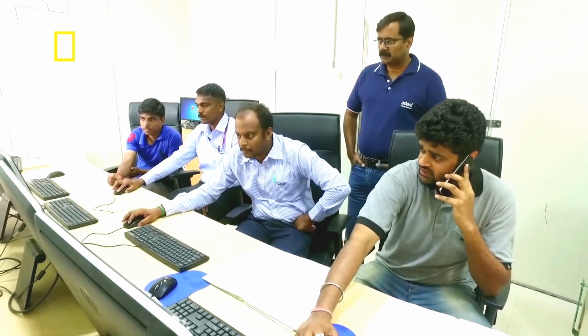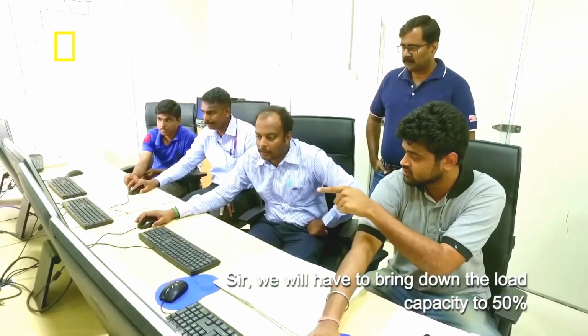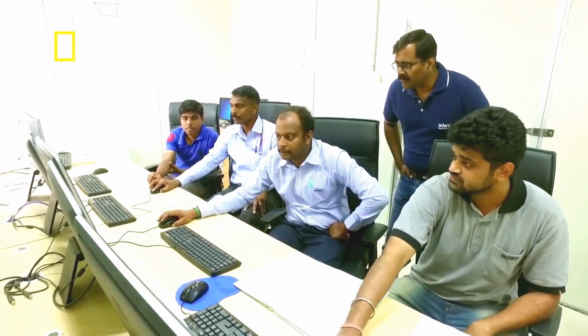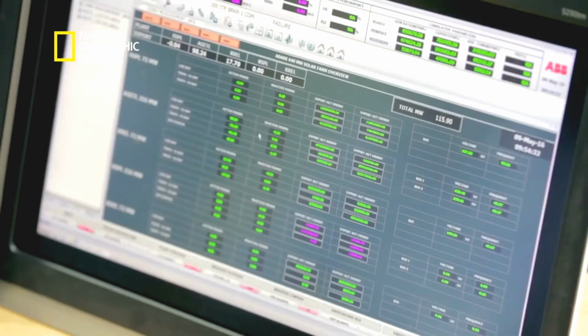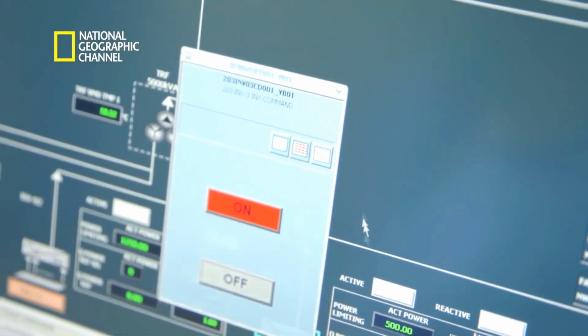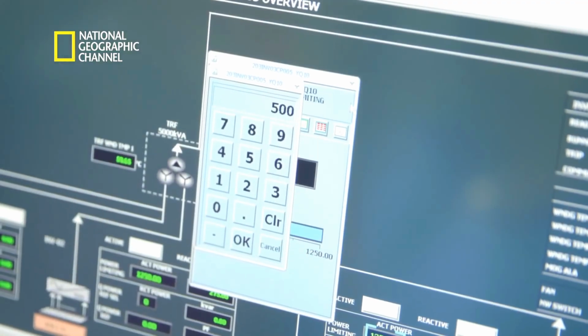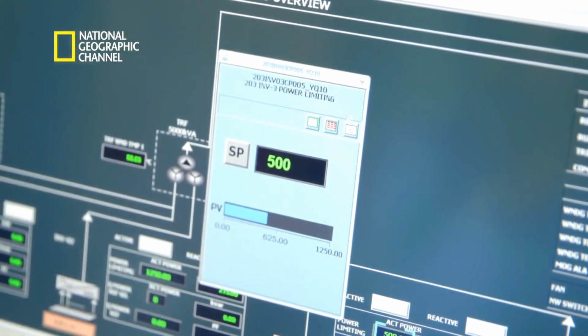Okay sir, we'll reduce it up to 50% of the present load. We are at 50 megawatts now, and we have to make it 25. Let's set the point to 25 megawatts now. Done? It's responding? Perfect. Now, suppose my inverter is generating 1 megawatt at a given point of time, and I want it to generate less, I can give a command from the SCADA, from the screen, and it will generate only 500 kilowatts, as per my requirement or as per the grid demand.